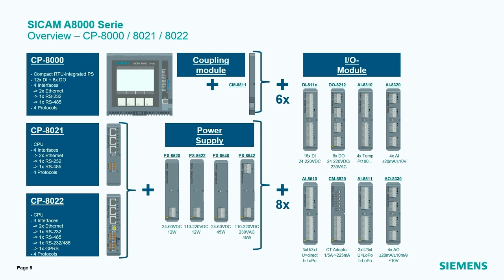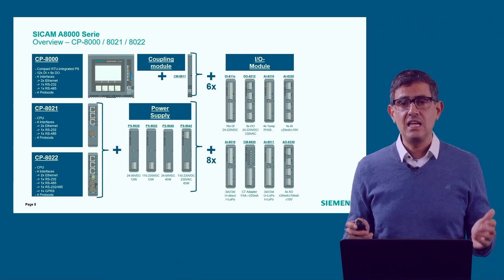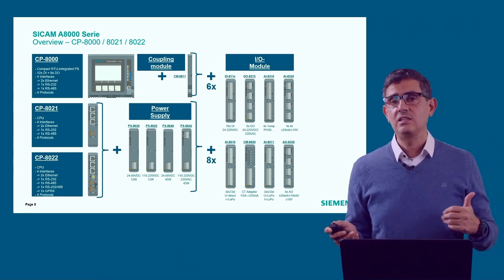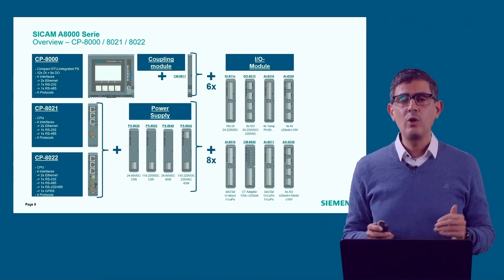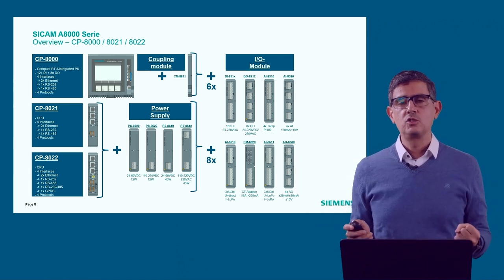You have modules for direct measurement from temperature transducers of the type PT100, for example the AI8310. You have also modules for measurement of transducers like 20 milliampere or 10 volts — the AI8320. You can also measure three-phase systems through the modules AI8510 or AI8511, which use low-power current inputs of 225 milliampere. To connect a three-phase system to one of these modules you need the converter CM8820, which adapts the current transformer signal of 1 or 5 ampere to the required low-power signal and wires directly to the AI module. There is also a module for analog output of 20 milliampere or 10 volts, so any measurement that comes to the RTU can be converted to an analog signal.